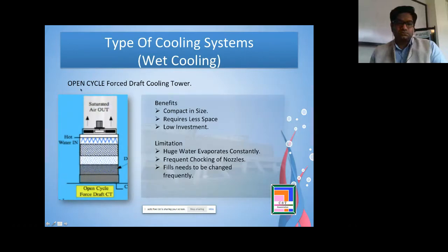Then some companies went to the open cycle forced draft cooling tower. In a forced draft cooling tower, the concept is the same; the only difference is that we spray the water on the fills, and the fan is on the top and draws the air, which maintains a liquid to gas ratio of 1.5 and cools the water. The benefit is that it is compact in size, because we use a different LG ratio, and requires less space and low investment. The limitation is that a huge amount of water again evaporates constantly, nozzles choke frequently, and the fill needs to be replaced every year, or every 6 months.